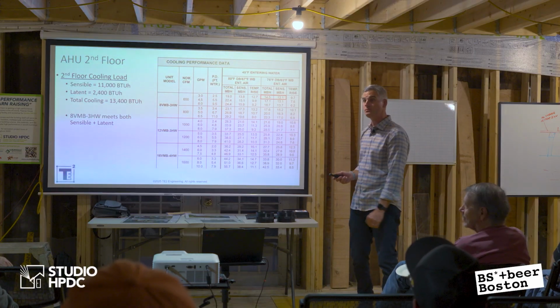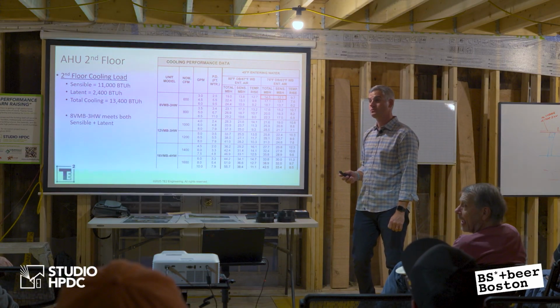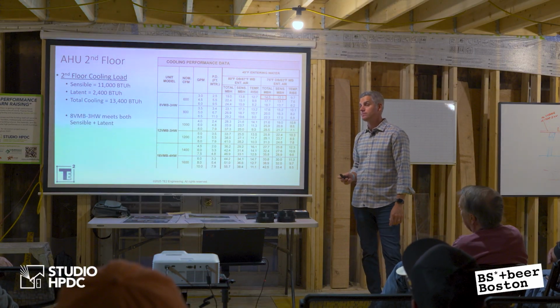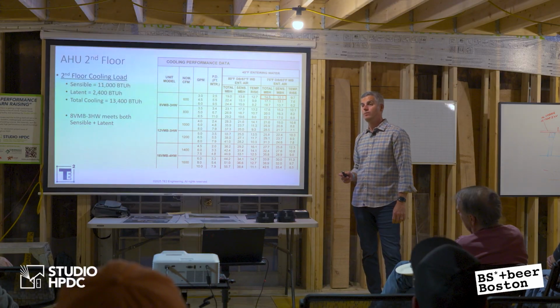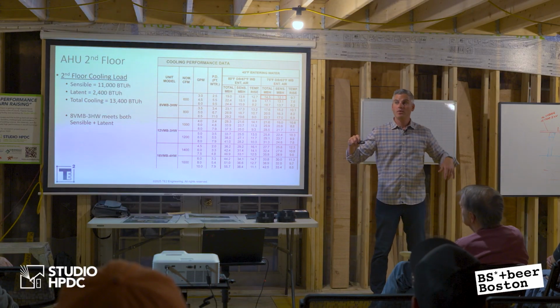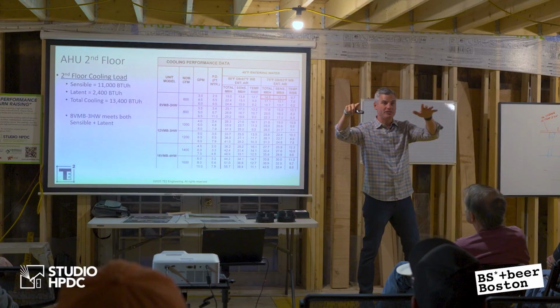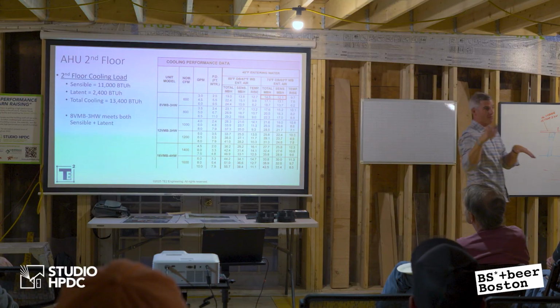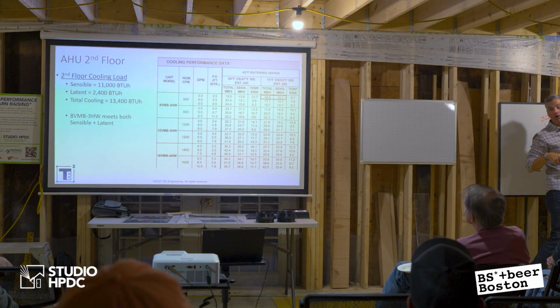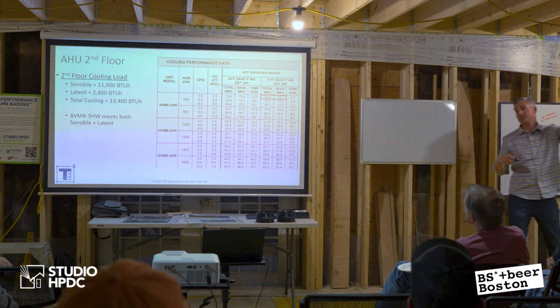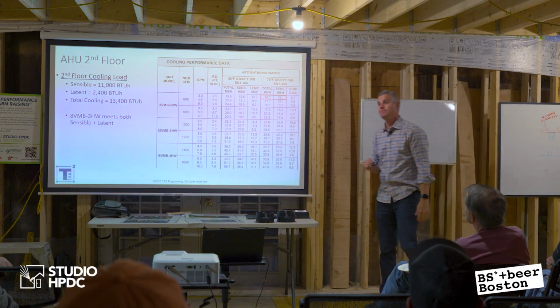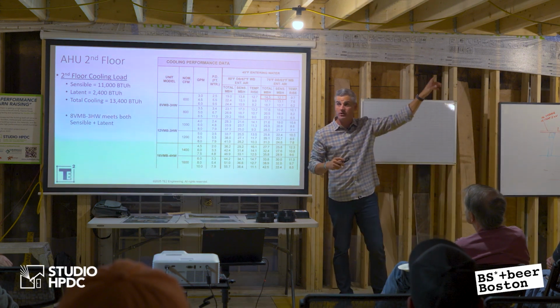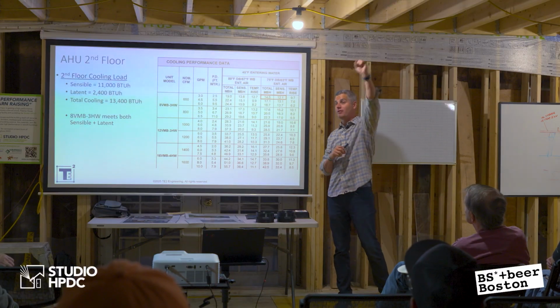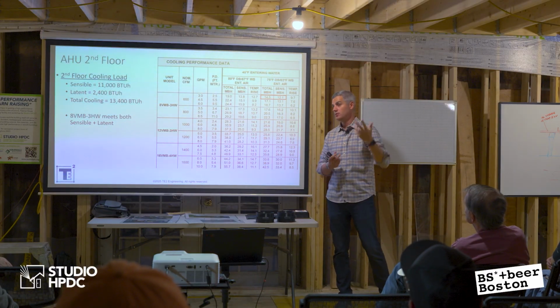Are you accounting for the spaces being connected? It's an open stairwell. So does this heat and humidity get up there? I'm defining the open space as the open space in the first floor zone, the bathrooms, and the stairwell going up the stairs. At the top of the stairs, the second floor system picks up. You will get a little stratification going up the stairs, but we have a thermostat upstairs and a thermostat downstairs, so we'll be able to keep that.